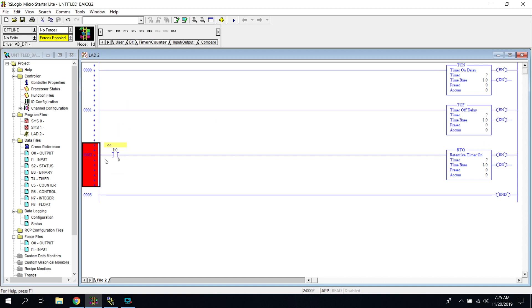The last one is our retentive timer. A retentive timer will actually accumulate time to the preset and it will retain it — it won't lose it. So if we wanted to change a filter every 30 days, we would use a retentive timer to count those days, because it would never stop. And if the power goes out, it would not lose that time base.